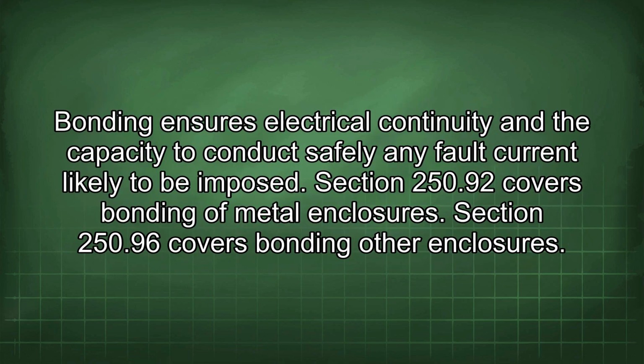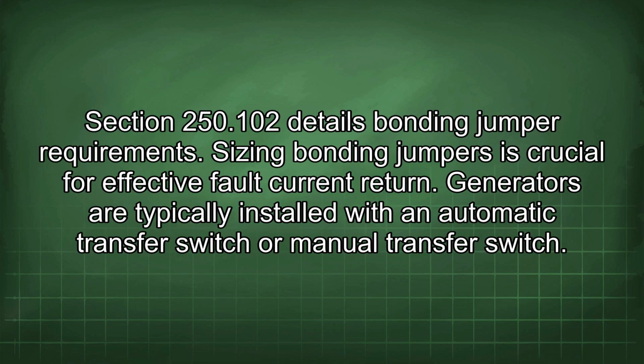Bonding ensures electrical continuity and the capacity to conduct safely any fault current likely to be imposed. Section 250.92 covers bonding of metal enclosures. Section 250.96 covers bonding other enclosures. Section 250.102 details bonding jumper requirements. Sizing bonding jumpers is crucial for effective fault current return.